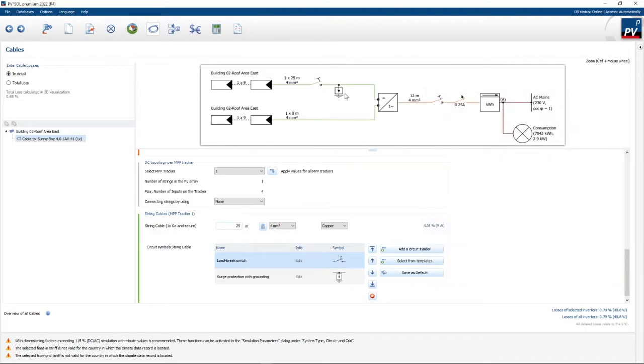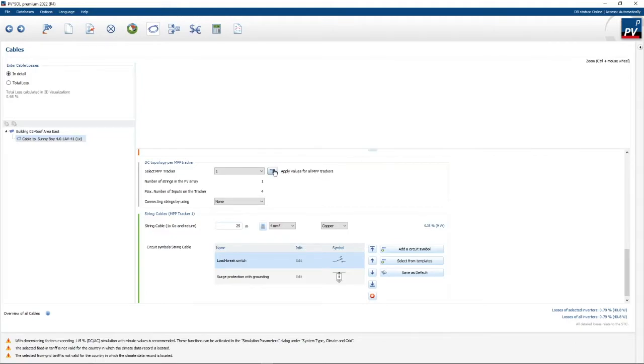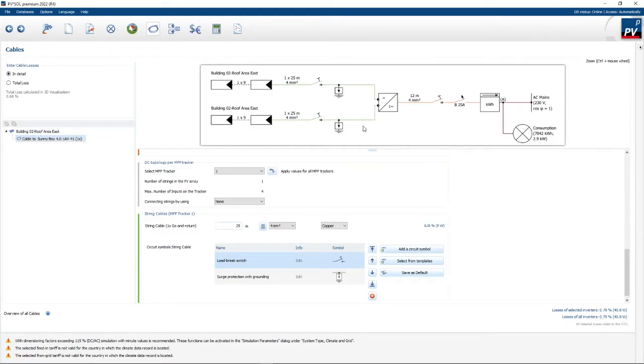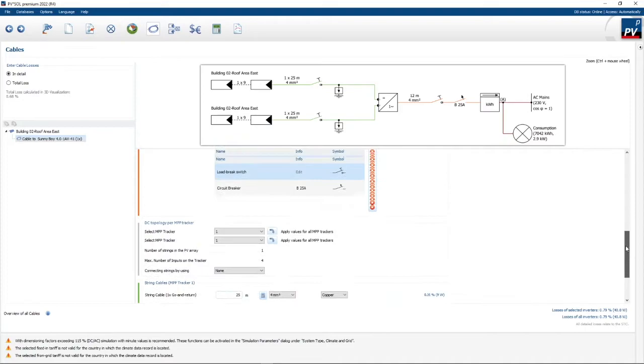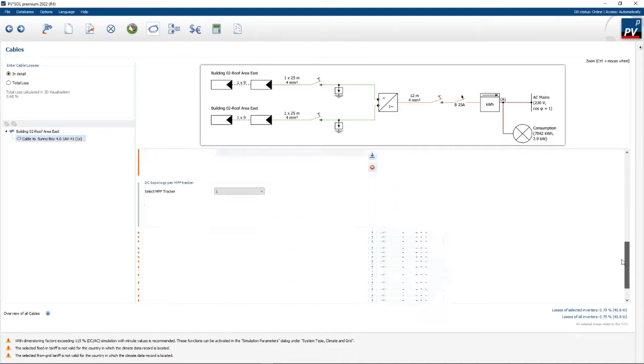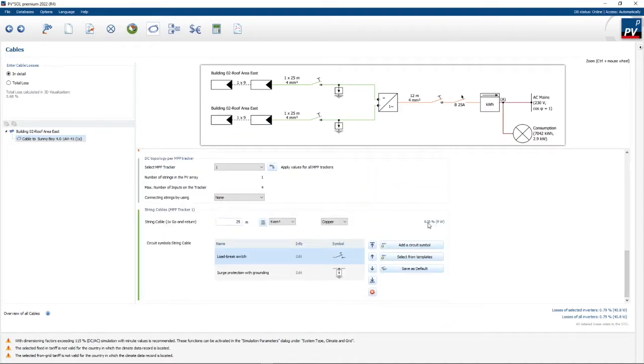You can see my isolator and surge protection. I can also apply it for the second string by clicking 'apply for all MPP trackers' so I've got it on all trackers. In total, PV Sol will specify the losses for us: cable loss is 0.35% and inverter losses on the AC side are 0.79%, all at standard test conditions.